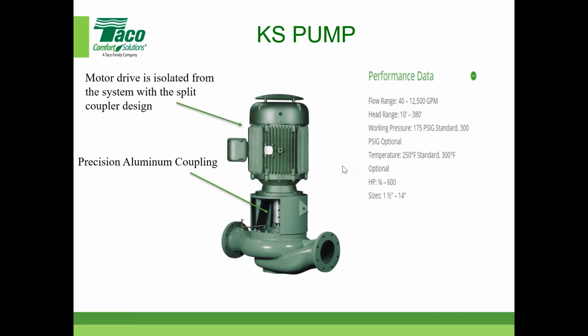At our facility, we pressure test the pumps after they're assembled. Not flow and head test, that's a whole different animal. We've done that initially, but not once the family is out there, we have to meet the curves, and we do. Nonetheless, we pressure test them to 1.5 times working pressure to ensure there are no leaks or porosity in the casing.